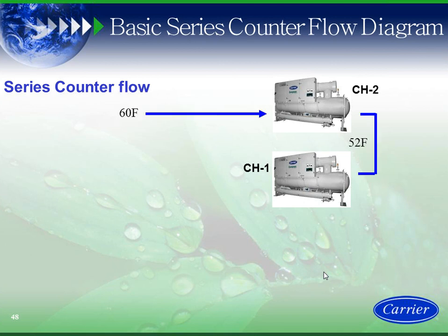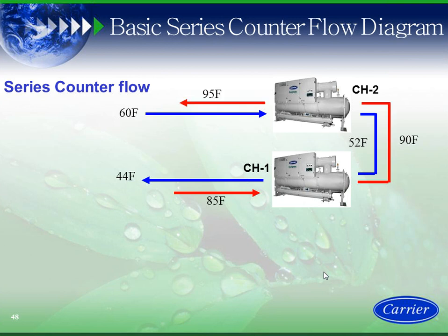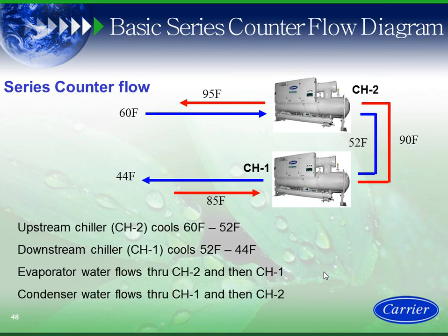If we look at series counterflow, basically I have 60 degree entering return water, entering chiller 1, chiller 2, and leaving 44 degree leaving chiller 1. Sorry. 85 degree entering chiller 1, 95 degrees leaving chiller 2. So my coldest entering condenser water hits my coldest leaving chilled water. Okay. Again, upstream chiller cools 60 to 52, downstream 52 to 44, and evaporator chiller 2 to chiller 1, condenser chiller 1 to chiller 2. And we'll go through some of these a little later here.